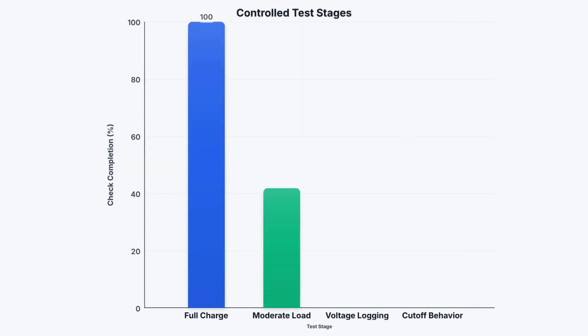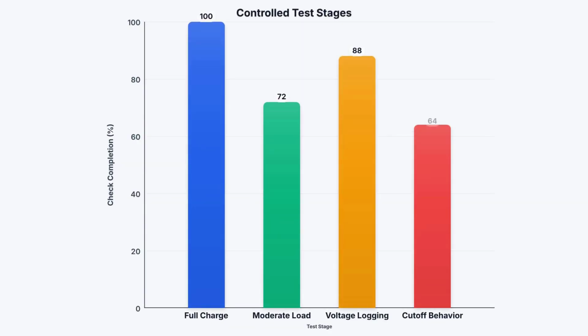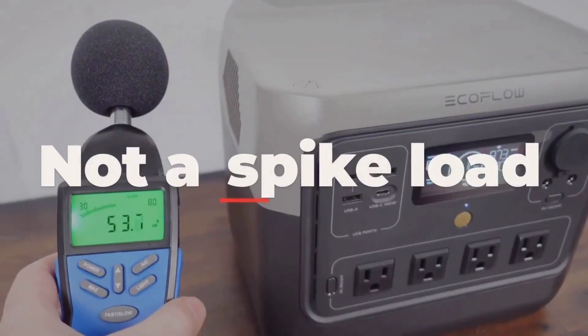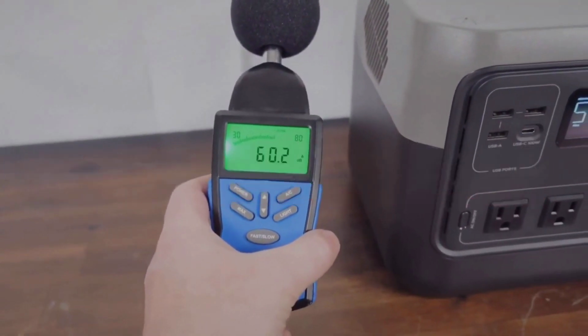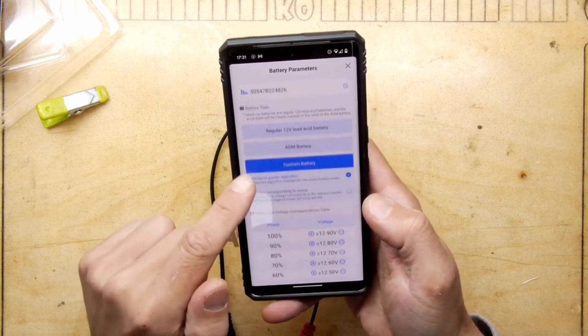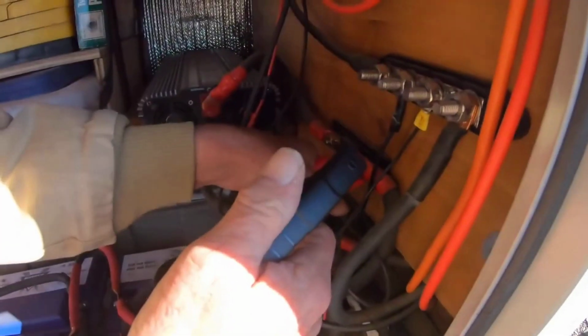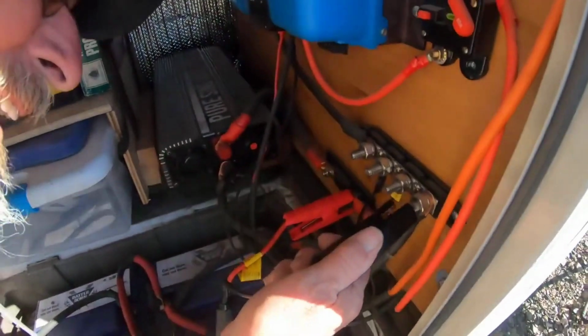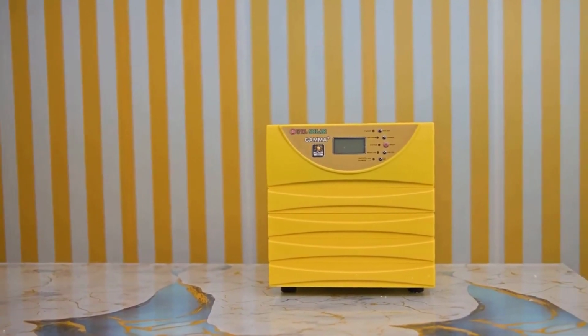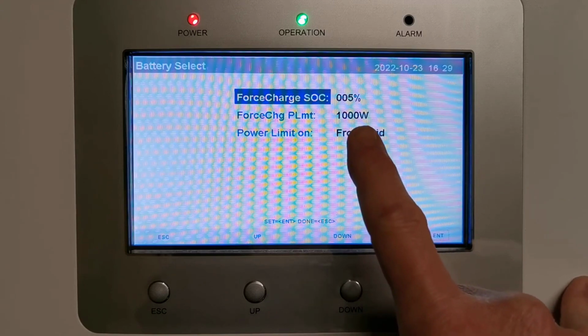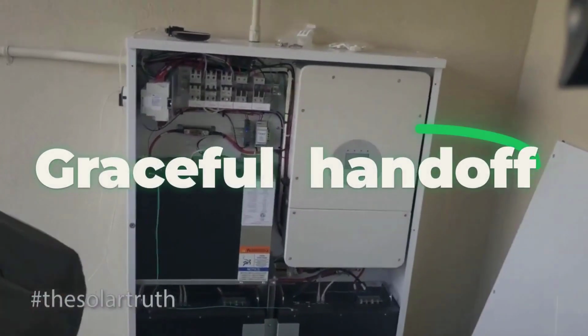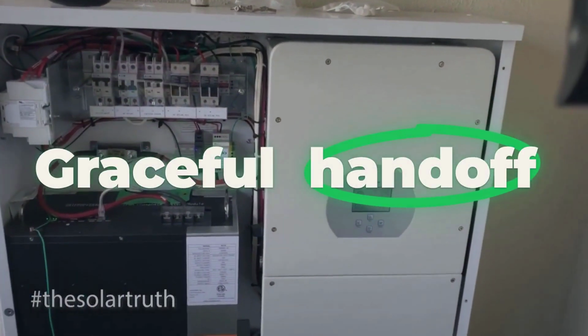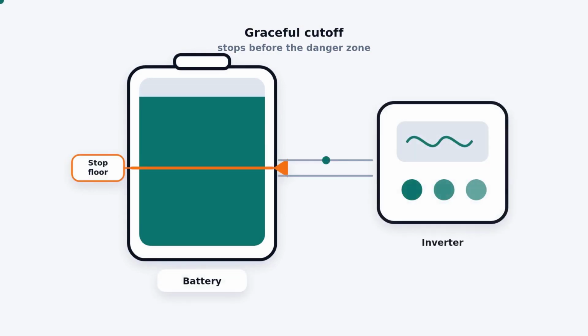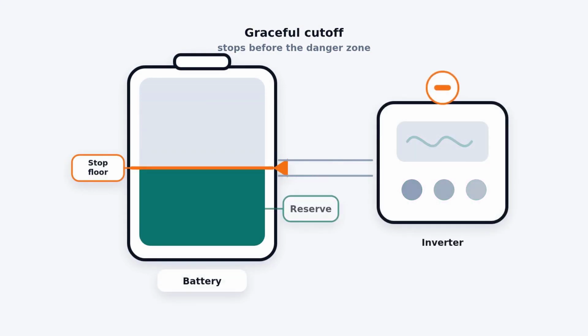Fully charge the battery. Apply a moderate, steady load. Something you run regularly, not a spike load. Log the state of charge and voltage every few minutes until the system stops drawing from the battery. Write down where it stopped, how it stopped, and whether anything abruptly cut out. Then raise the discharge floor by 10 to 15% above where you previously saw cutoff, and run the same load again. What you are looking for is a graceful handoff. The inverter stops pulling from the battery earlier, a usable reserve remains, and nothing collapses. That is the setting doing exactly what it is supposed to do.